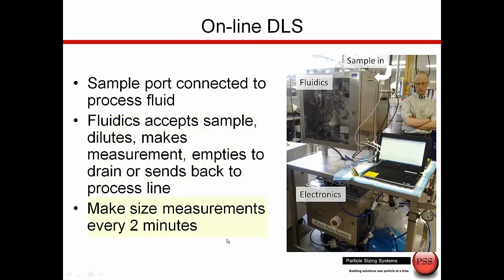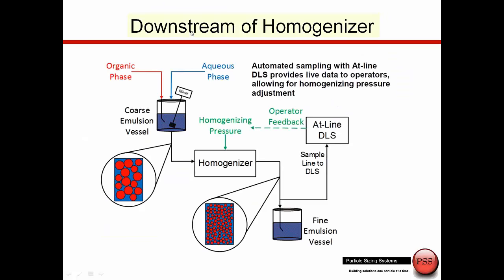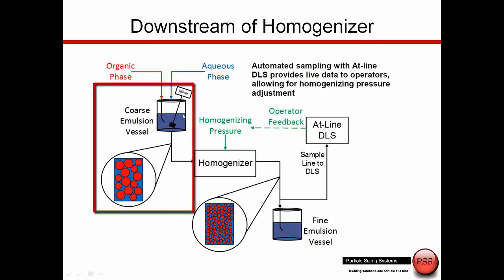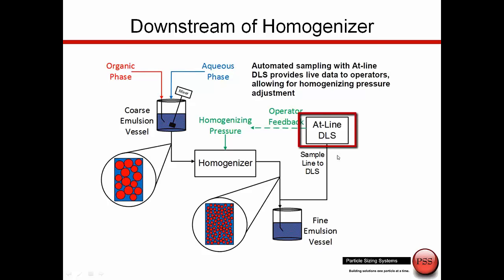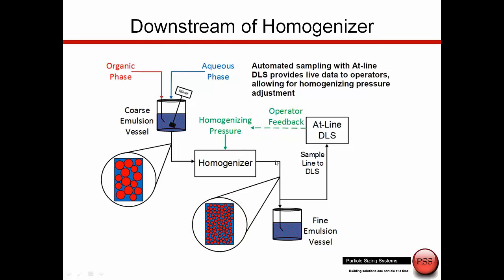The cycle time was on the range of about every two minutes. The process we're monitoring is downstream of a high-pressure homogenizer. Prior to the homogenizer, we have the organic phase and the aqueous phase going into a mixer for coarse mixing. Then this mixed sample comes into the homogenizer where we do the very large size reduction — making large particles very small. It's downstream of this homogenizer where we'd like to take the measurement, and through operator feedback, control this homogenizer to generate particles at the optimum particle size.